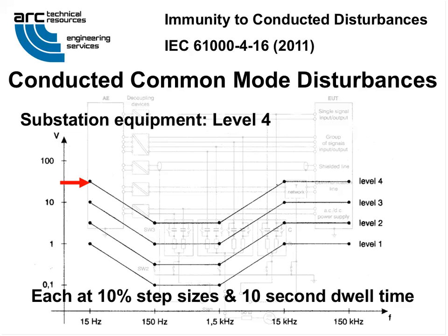So for margin testing, as I mentioned, the manufacturers usually have critical relay equipment. They don't bother with the dip. They just run it flat straight across. If they pass, they pass. That means they have some extra 10 or 15 dB of compatibility margin that indicates the product will be reliable in the field.